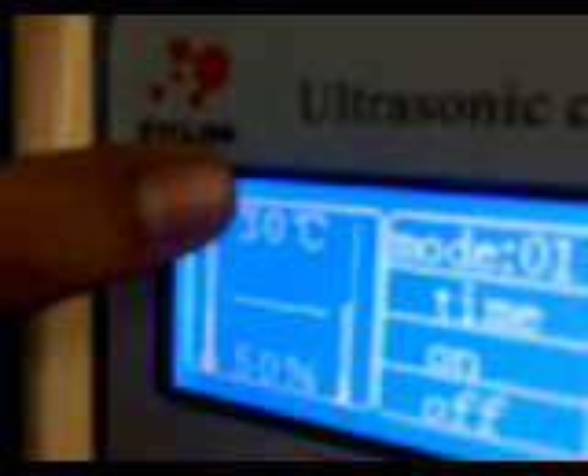So set the parameters at program number 1. The run time is 2 minutes. The on cycle is 2 seconds. Let us increase it to 4 seconds, and here I will say store. So now we can say start. On, turn off, then again on. You may see that the temperature is rising. To reach 50 degrees, the machine will stop, so that your sample does not get spoiled.